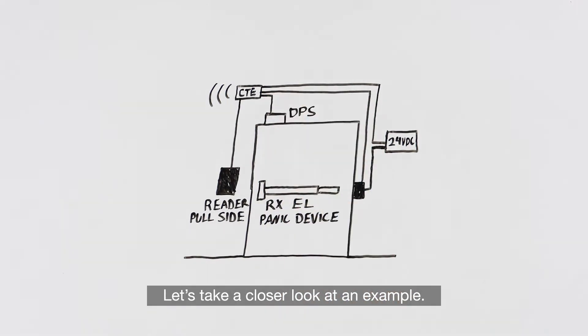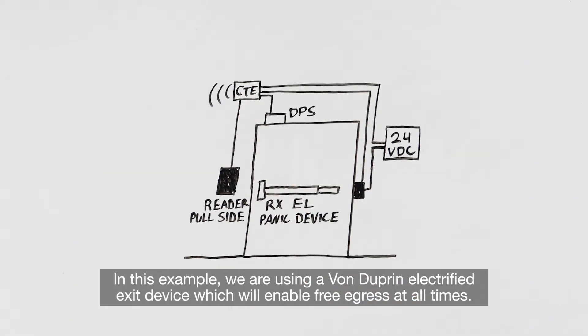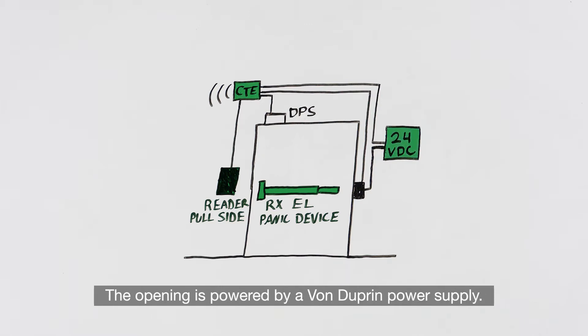Let's take a closer look at an example. The CTE is typically installed close to the opening in a secure location, perhaps in an adjacent closet. In this example, we are using a Von Duprin electrified exit device which will enable free egress at all times. The Schlage MT11485 reader is mounted to the exterior side of the door and is connected to the CTE. The opening is powered by a Von Duprin power supply.